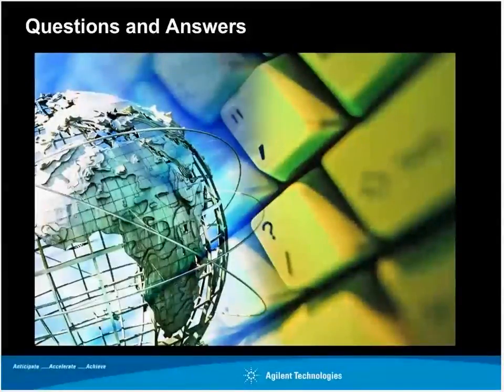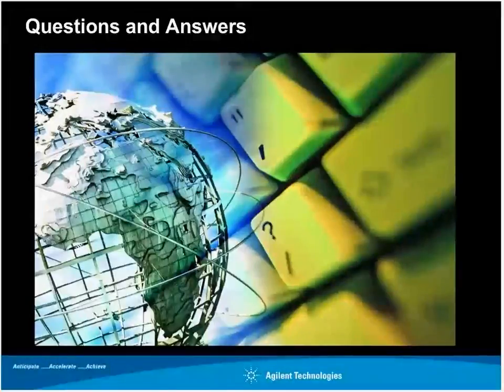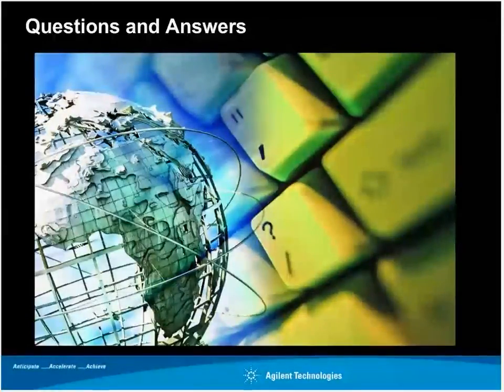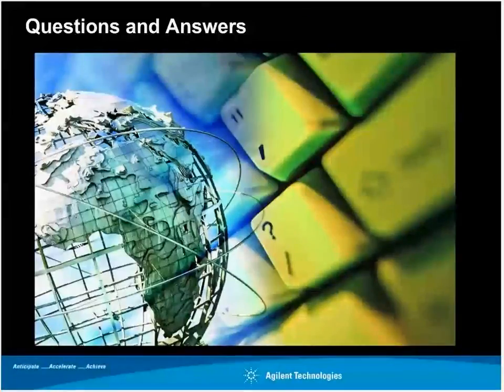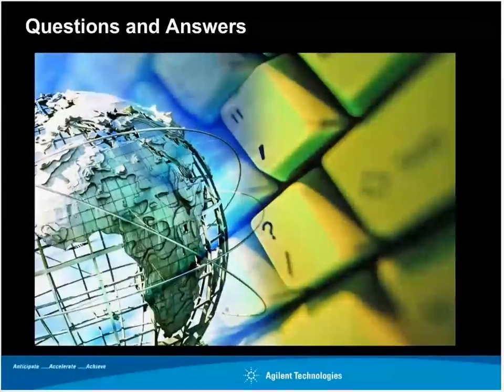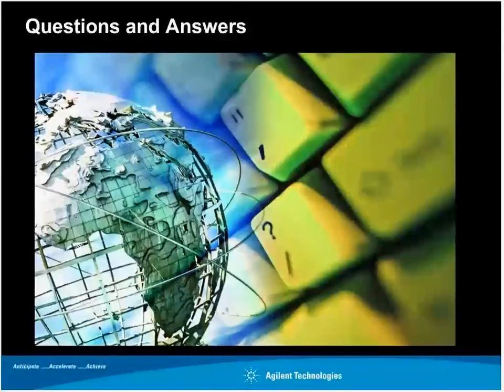we're changing our values, there's multiple things that we have to take a look at. Did a calibration provider give us a new uncertainty for the calibration service? Did our environment change? Did our procedure change that would affect the repeatability, the reproducibility of the process? So there's a few things that go into that before we can determine if the scope is changing. But if it gets to the point that the scope is able to change, contact your accreditation body to figure out what kind of change notices would have to be completed to ensure that you've got the most up-to-date information on your scope of accreditation.